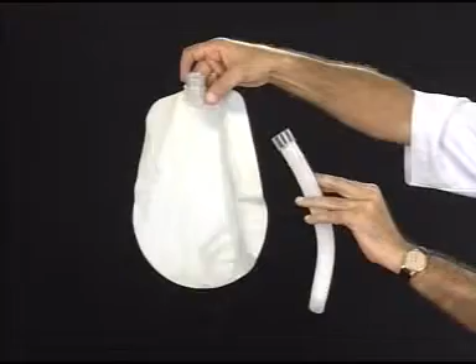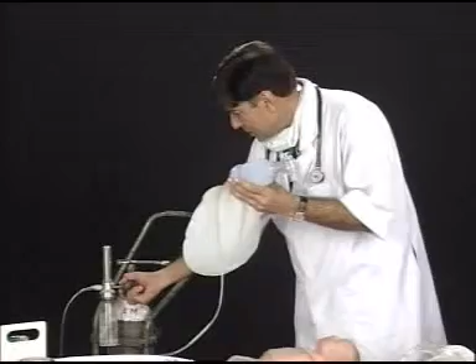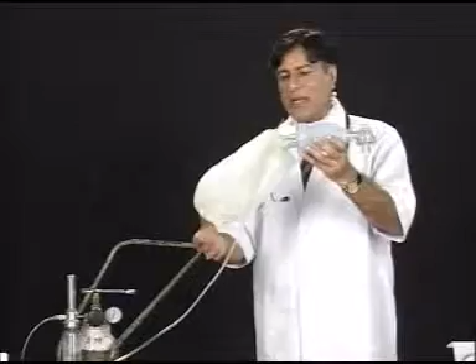In order to increase the concentration of oxygen inside the bag, one needs to attach an oxygen reservoir. So when the oxygen reservoir is attached and the oxygen flow is 5 to 6 liters per minute, then the oxygen starts flowing inside the bag and the bag starts inflating. So the oxygen is flowing from the cylinder or from the central source into the chamber, and from this chamber it is coming back into the oxygen reservoir. The rest of the oxygen goes into the air. When you use this bag, then the bag will take oxygen from the oxygen inlet and oxygen from the oxygen reservoir.